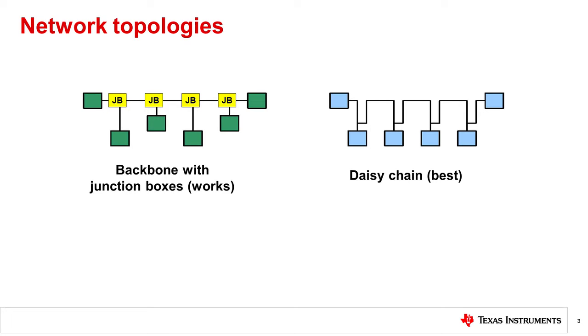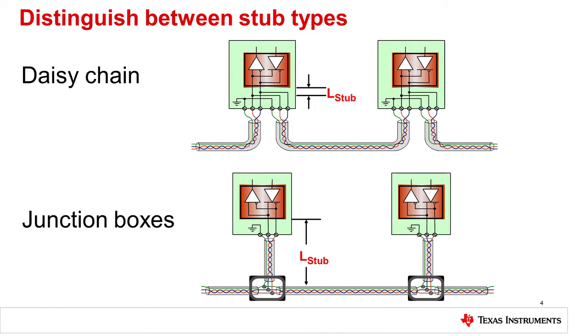If a non-ideal network topology must be used, it is best to insert a repeater node at each junction. The stub length is defined as the T-junction from where three lines intersect to the device pins. For the daisy chain topology, this occurs on the PCB board at the two joining transmission cables and the traces to the RS-485 transceiver. For the junction box approach, this occurs at the main transmission wire and the joining wires into the device pins. Because the daisy chain topology allows for much smaller stub lengths, this helps reduce reflections into the main transmission line, which is the main reason this topology is preferred.